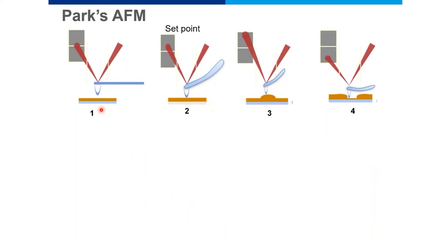Let's understand the mechanism to generate an image. First, the laser is aligned into the photodiode exactly at its center, with no tip-sample interaction — the tip is in air. Then we slowly land the tip on the sample. The moment the tip lands, the cantilever bends, and the laser spot deviates slightly in the vertical direction from center. This deviation value is what we call the set point.